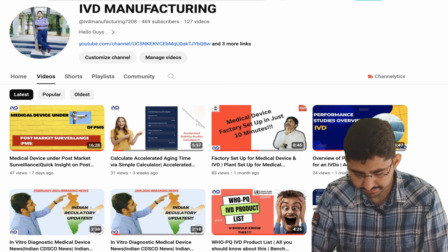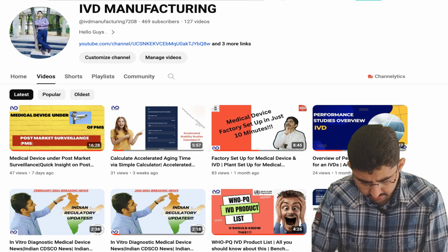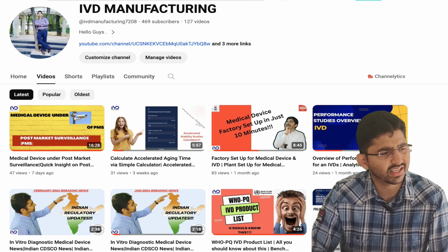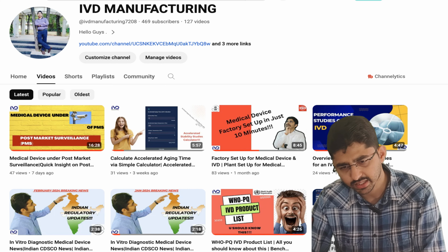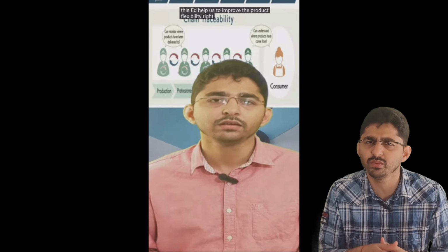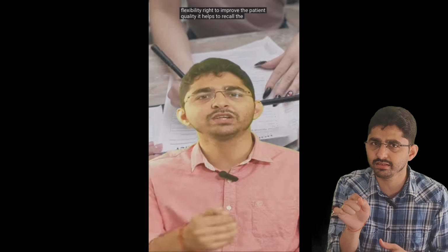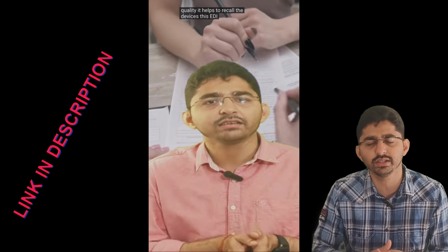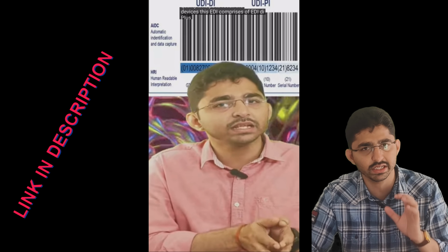The feedback form also has a word, UDI, somewhere, Unique Device Identification. This Unique Device Identification speaks of a unique property for a particular medical device. For example, if I am an employee of a company, I will have an employee ID. Similarly, the medical device also bears the UDI, on which I have already made a lecture. It was a short video. I am going to share the link in my description below. You can refer to that short one-minute video explaining what UDI is.